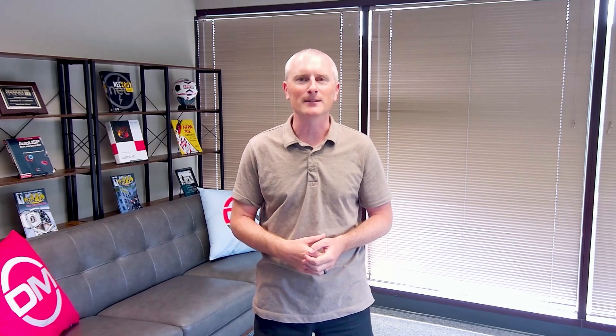For all electronic curves, the I² T curve is probably the one that varies the most in terms of how it's implemented — sometimes it's just on or off, sometimes it varies based on the short time delay value. There's really no standard for how manufacturers have implemented that part of the curve, so you need to be aware for the breaker you've chosen how that curve actually works.